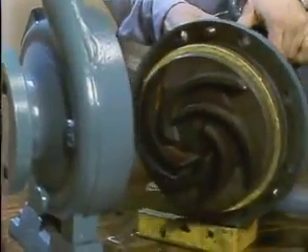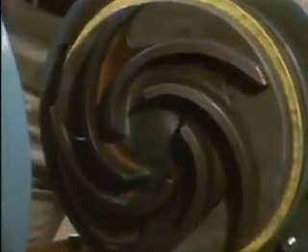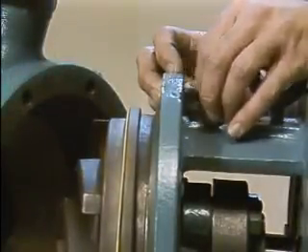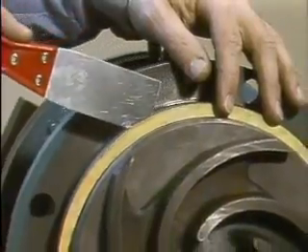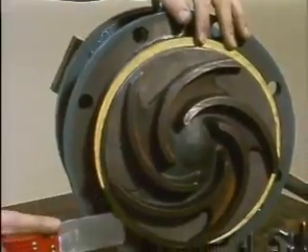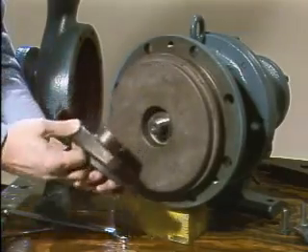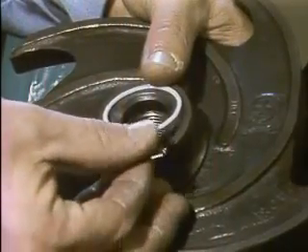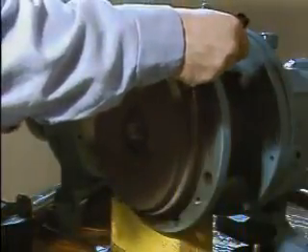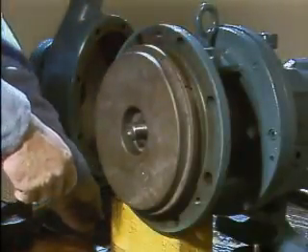Now the frame and the bearing housing can be moved to the side to allow for easy access to the remaining parts. The jacking bolts are also removed. Then the old casing gasket is taken out and discarded. A new gasket will be installed later. Next, the impeller is removed, and so is a small impeller gasket. The backplate is match marked with the frame to make reassembly and alignment of the components easier later on.